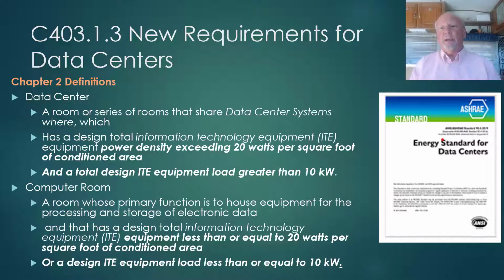Now, if you have just a computer room, a single room, how do you determine it's defined as a computer room? Its primary function is also to house equipment for processing and storage of electronic data, and it has an ITE equipment load less than or equal to 20 watts per square foot, or a design IT equipment load less than or equal to 10 kW. So smaller computer rooms that meet this definition do not need to meet the requirements of ASHRAE 90.4, but they still need to meet the requirements for HVAC system efficiency, economizer, envelope, and lighting requirements of the code.